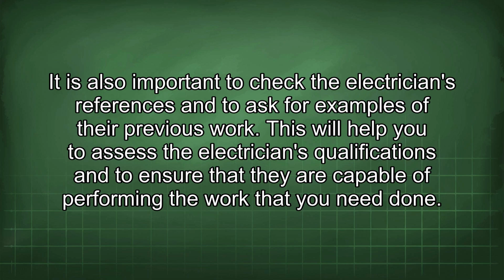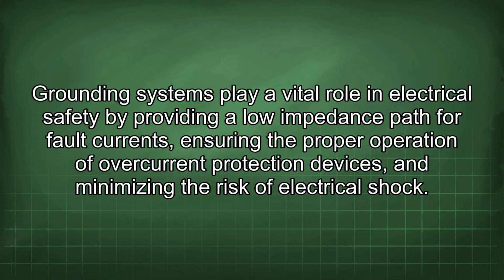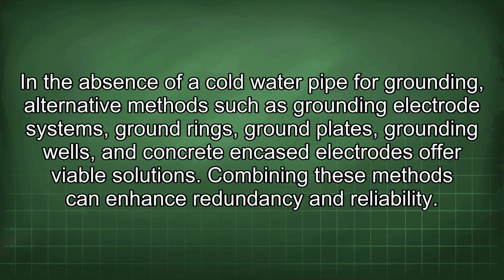Grounding systems play a vital role in electrical safety by providing a low impedance path for fault currents, ensuring the proper operation of overcurrent protection devices, and minimizing the risk of electrical shock. In the absence of a cold water pipe for grounding, alternative methods such as grounding electrode systems, ground rings, ground plates, grounding wells, and concrete encased electrodes offer viable solutions. Combining these methods can enhance redundancy and reliability.